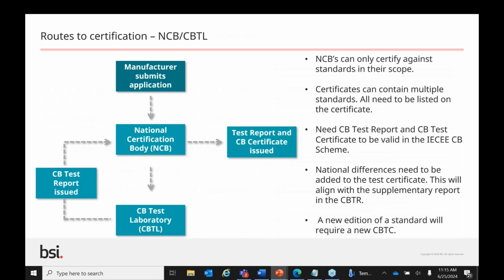So how do I get there? The most common route of achieving a CB test report and certificate is with an NCB, or certification body, and their appointed test lab, CBTL. An application for a CB certificate can be made to any NCB, such as BSI. The NCB will then instruct their CBTL to carry out the required testing to an IEC standard or standard within their scope. The CBTL will then go on to issue that test report back to the certification body, who issue the final CB certificate along with the test report.